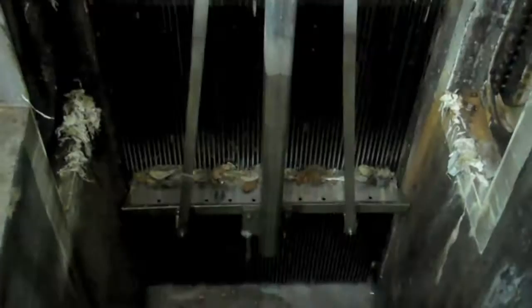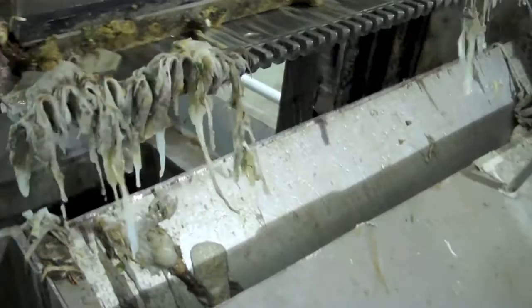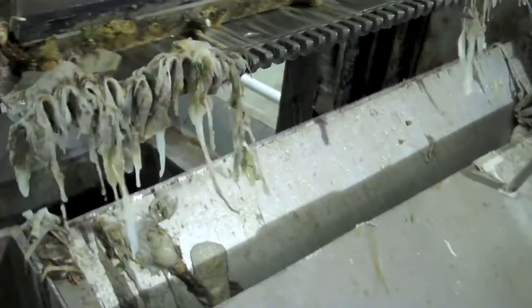And how does it fish it out down there? Basically, there's an arm down below that goes back and collects the material from the screens, brings it up and runs it through a grinder. All the water is running through a screen — it doesn't get past here without going through the screen. And then once it lifts it out of there it grinds it up, and it's pumped upstairs for washing and compression to remove any excess water and then goes into a dump truck to the landfill.